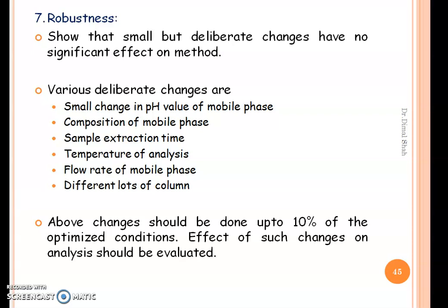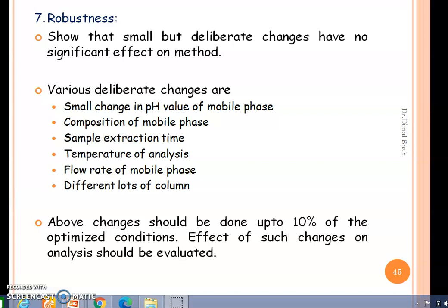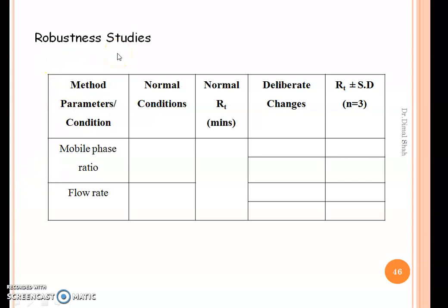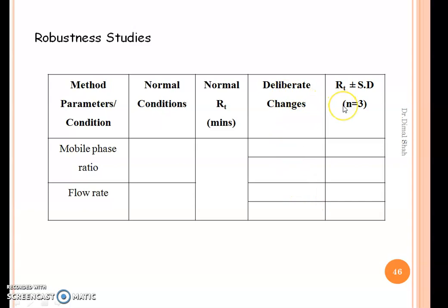These small changes should be done up to 10% of the optimized condition, and the effect of such changes on the analysis should be evaluated. The table for reporting robustness study parameters includes method parameters such as change in mobile phase ratio or flow rate, the normal condition and normal retention time, the deliberate changes made, and the effect of those deliberate changes on the retention time of the drug.